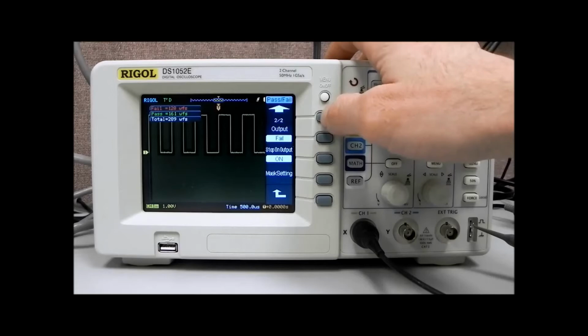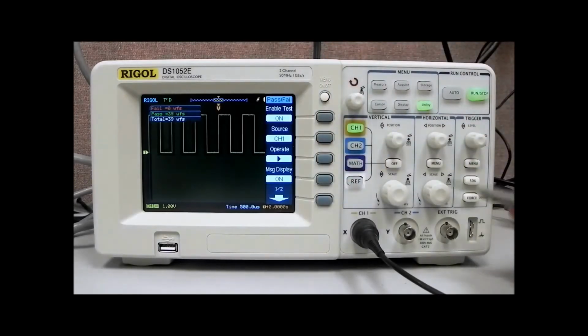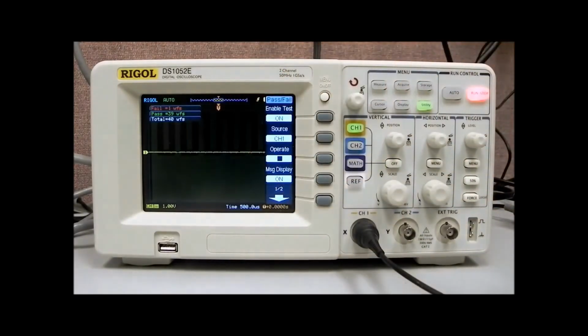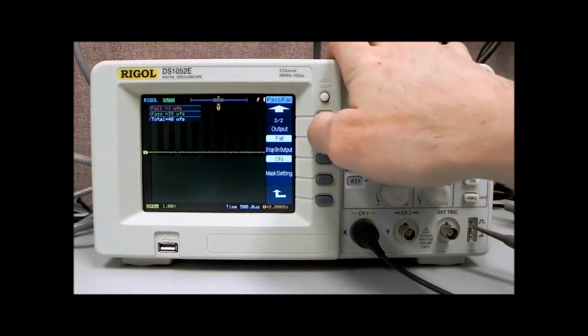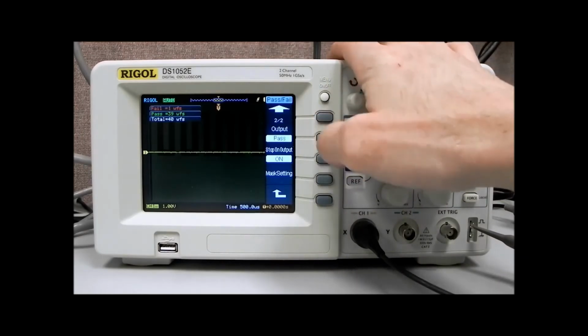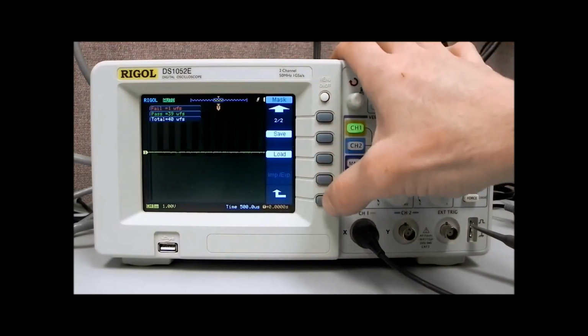So that means that when it fails, the box is going to stop, and you'll see it will quit taking waveforms. So we've gone into stop mode, and now we've only had one fail, but that fail has stopped the instrument from taking any more data. It's also through the output on the back of the instrument, it's also disabled or sent a failed signal. We've configured it to do that by using the output fail, and then we can also do an output on pass if we'd like. So very flexible.